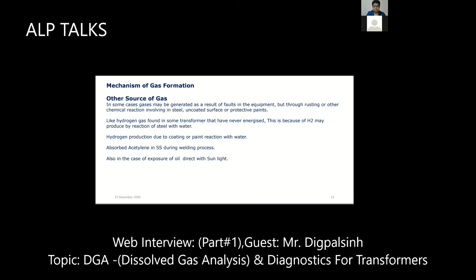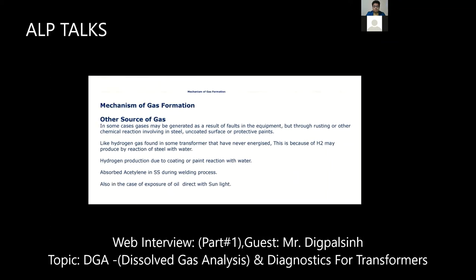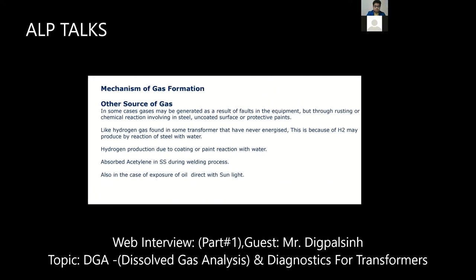Hydrogen gas is found even in transformers that have never been energized. As I said, even if no fault is there, you can see hydrogen is there. This is because H2 may be produced by the reaction of steel with water. We find some H in the transformer oil and there is oxygen, so it creates H2O. Then there is a reaction of steel with water, hydrogen is separated from H2O, and hydrogen will be there. Again, hydrogen is produced due to coating or paint reaction with water.